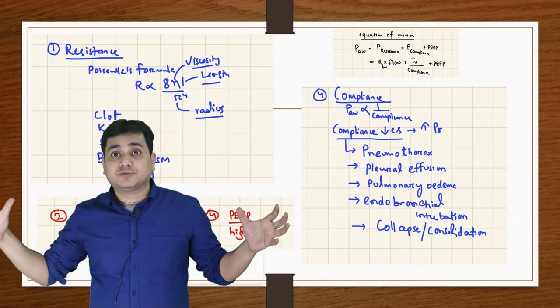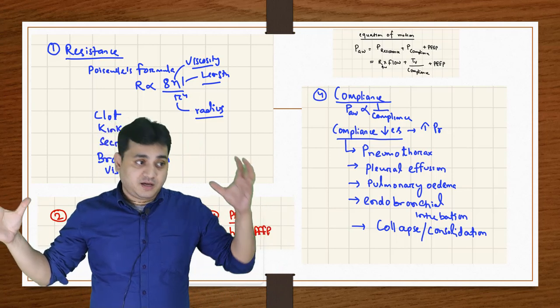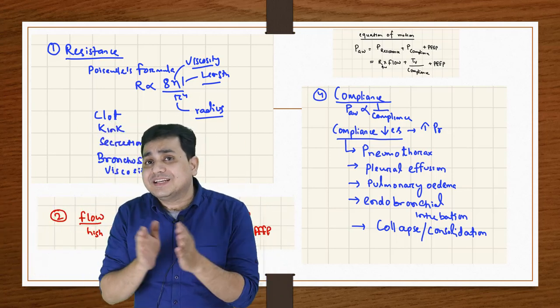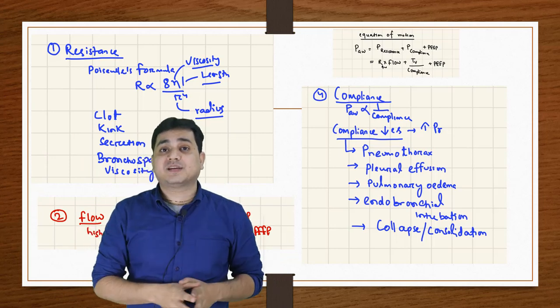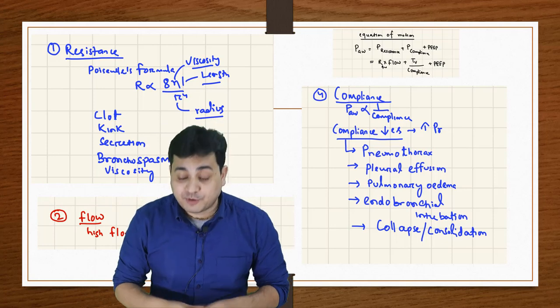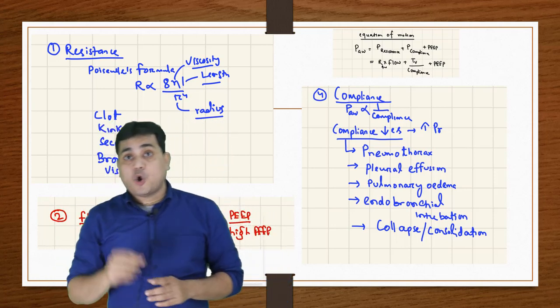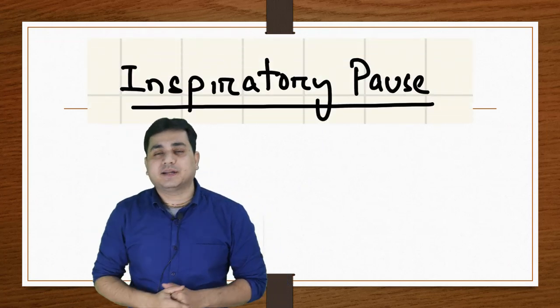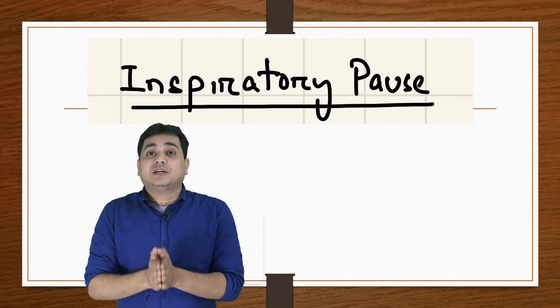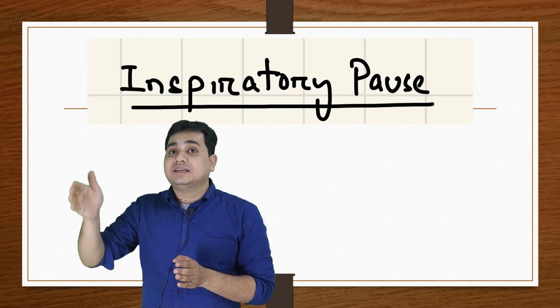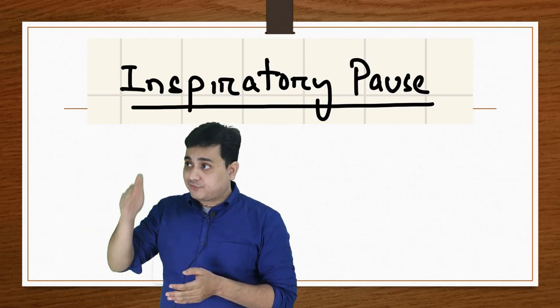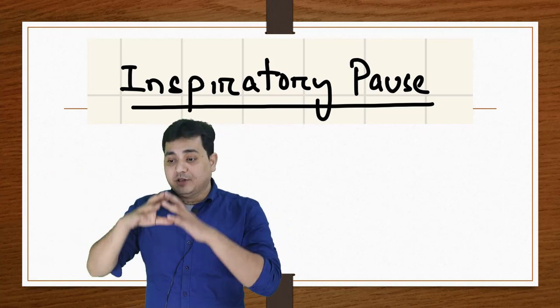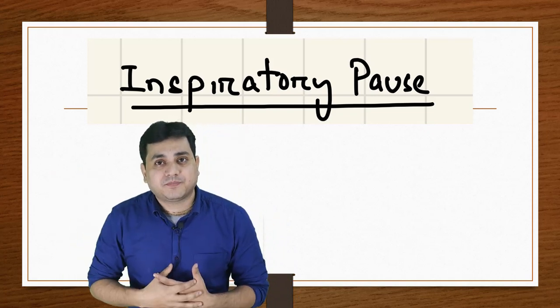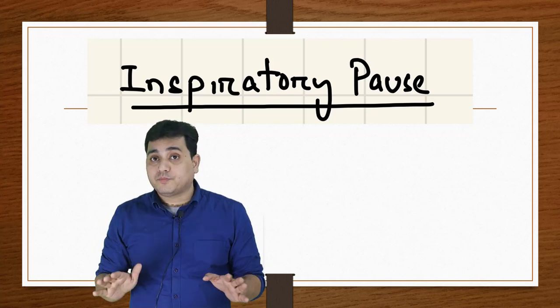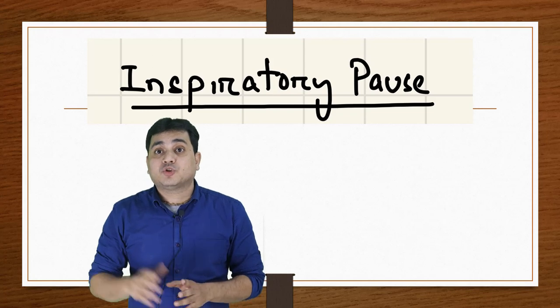Now we have a huge list of differential diagnoses, resistance problem and compliance problem. How can we differentiate these two so that we have few differentials to deal with? Then we have to apply what we call an inspiratory pause or T pause or T plat. If you put an inspiratory pause time in the ventilator, which is there in all ventilators, you are stopping the flow for a certain period of time inside the lung. Because you are stopping the flow, the pressure that is there inside the lung is the plateau pressure. Correct? There is no flow, so there is no resistive force or pressure. So that is the plateau pressure.